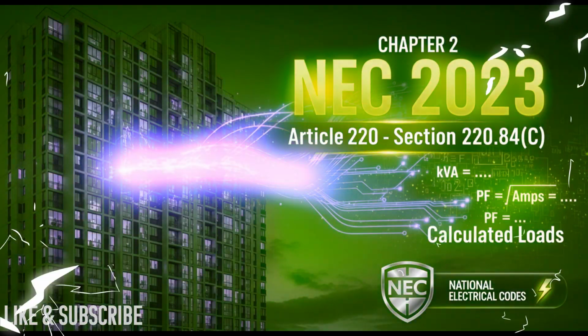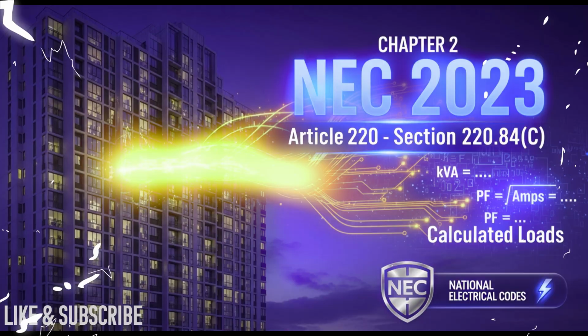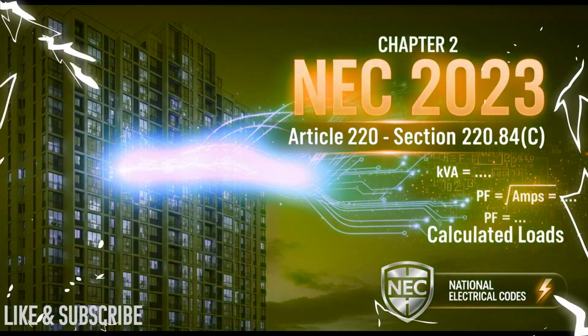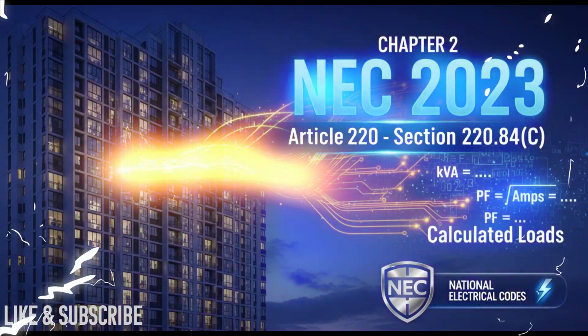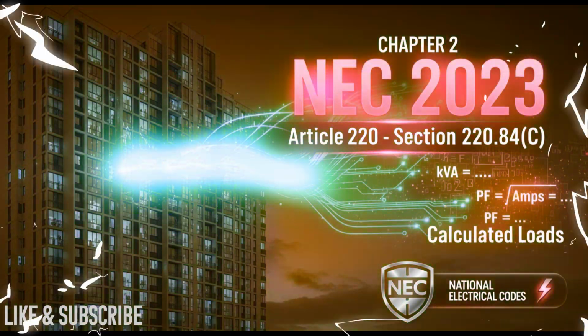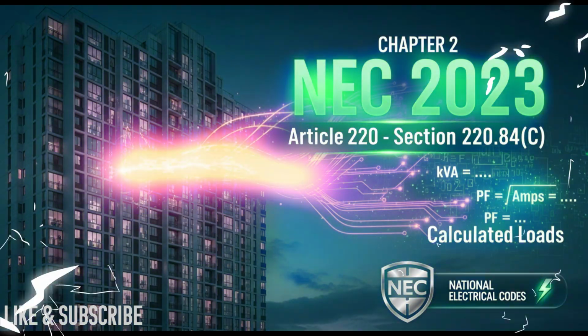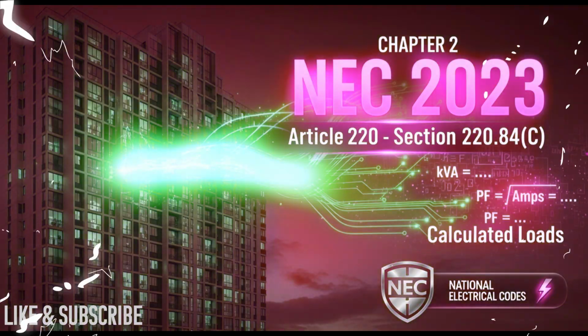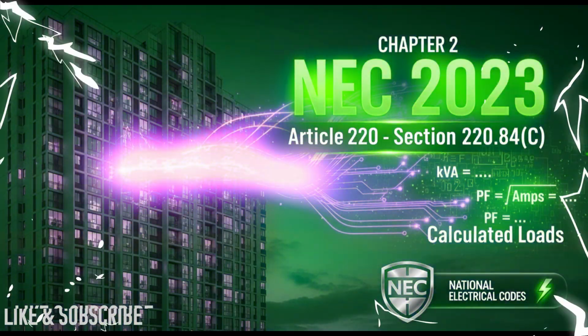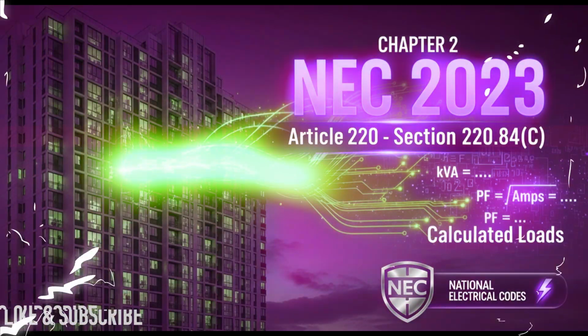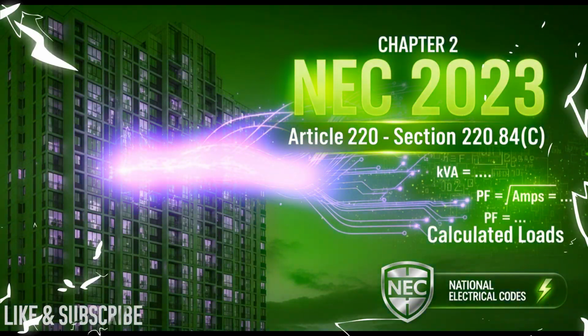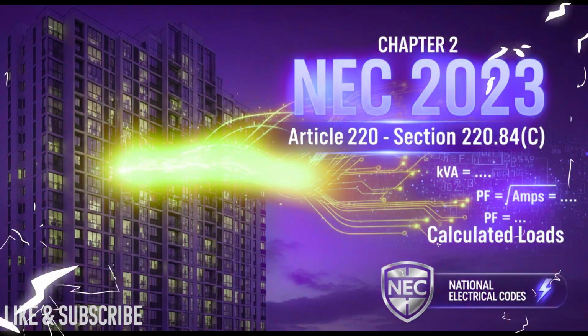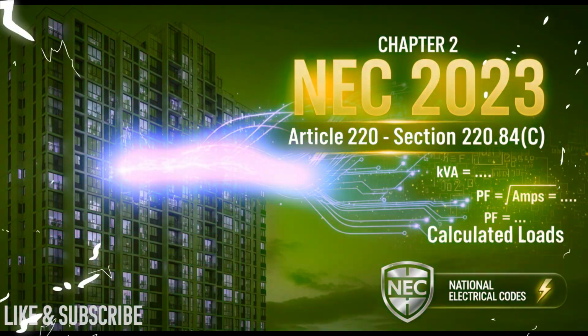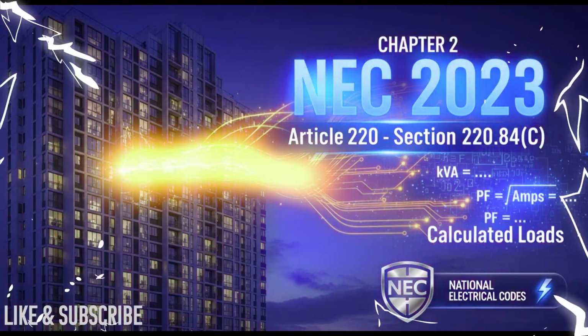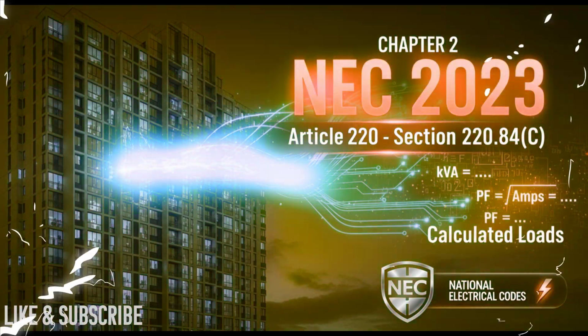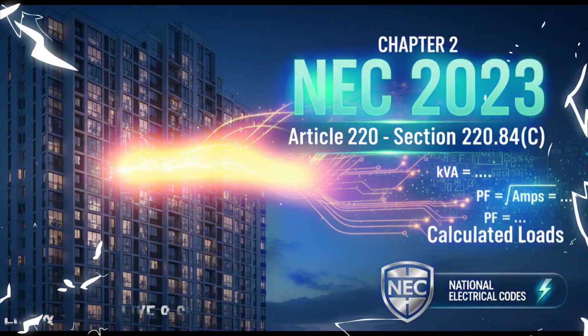So the logic is you're either running the heat full blast in the winter or the AC full blast in the summer. But very, very rarely are you doing both at maximum capacity at the exact same time across the entire building. Right. That makes practical sense. It does. And by only taking the larger of those two major loads, the calculation stays safe for the peak demand season, whichever it is, but it avoids forcing the designers to size the main service conductors, the transformers, all that expensive gear, for a combined load that will almost never actually happen. Precisely. The cost savings just from that one logical assumption, not doubling up on heating and cooling loads, can be absolutely substantial on a large project. It prevents major, unnecessary expense on the main electrical gear.